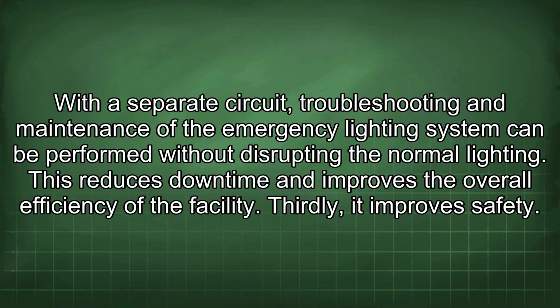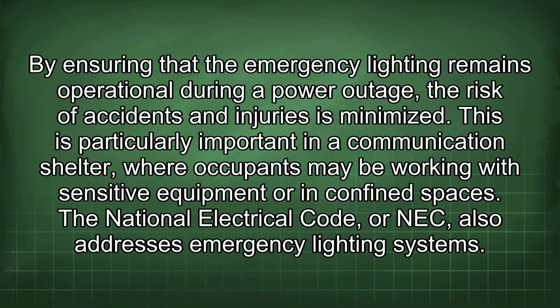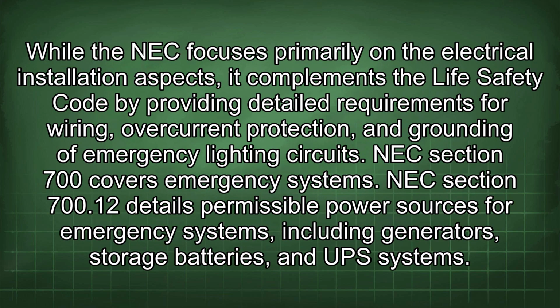Thirdly, it improves safety. By ensuring that the emergency lighting remains operational during a power outage, the risk of accidents and injuries is minimized. This is particularly important in a communication shelter where occupants may be working with sensitive equipment or in confined spaces. The National Electrical Code, or NEC, also addresses emergency lighting systems. While the NEC focuses primarily on the electrical installation aspects, it complements the Life Safety Code by providing detailed requirements for wiring, overcurrent protection, and grounding of emergency lighting circuits.